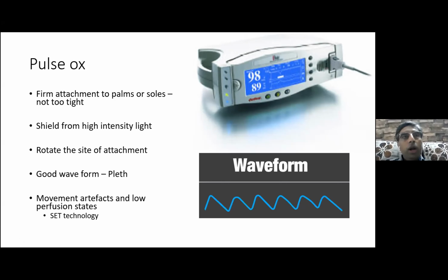To avoid or lessen the impact of those artifacts and to pick up a good waveform even during low perfusion, that is even in shock states, there are pulse oximeters which have a technology called SET. One of the classical and foremost principles used in this technology is Masimo. That is why Masimo technology is indicated in babies who are in shock, or to avoid even the movement artifact. So if you take care of all these things, then pulse ox is the best instrument to rely on for oxygenation.